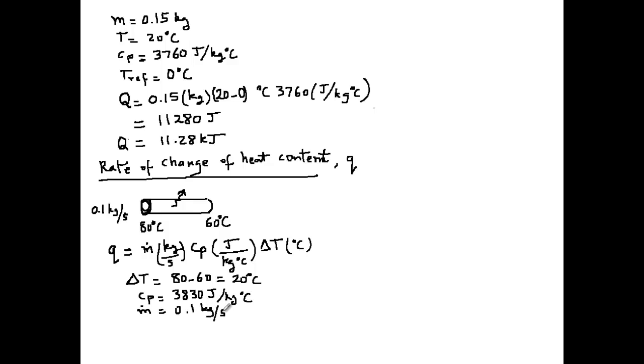So, we can go ahead and enter all the values in the equation. So, we have lowercase q equals 0.1 kilograms per second times 3830 joules per kilogram degree C times 80 minus 60 degrees C. This gives us the value for q as 7660 joules per second.